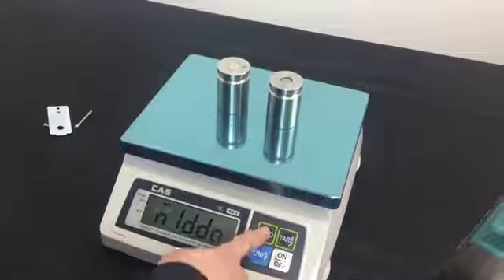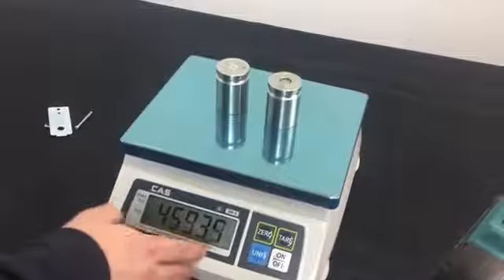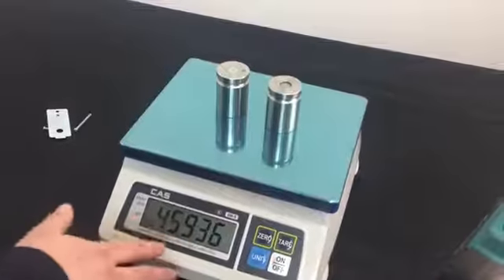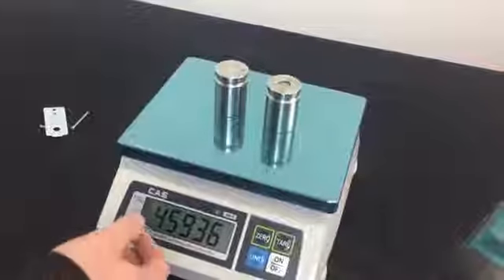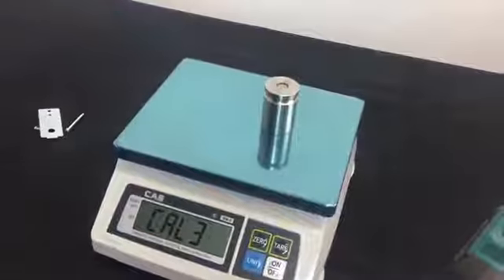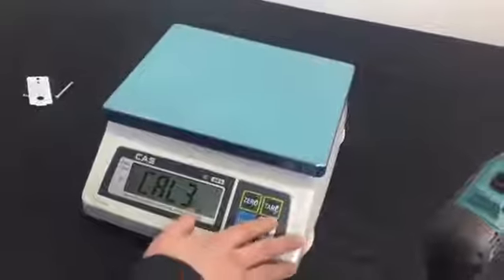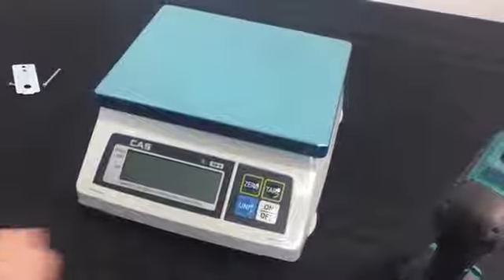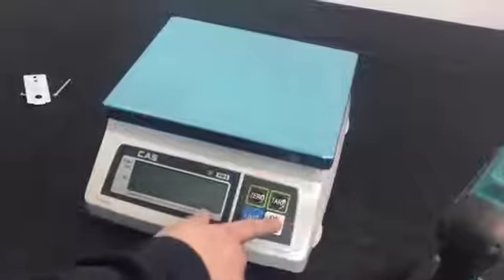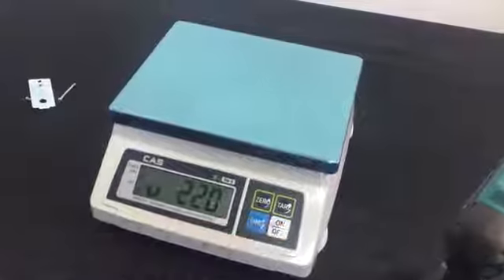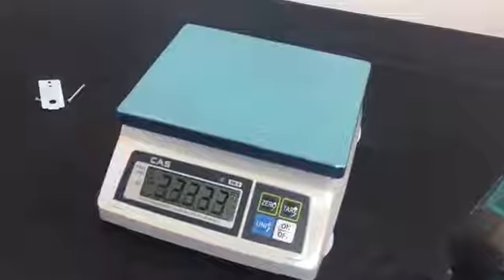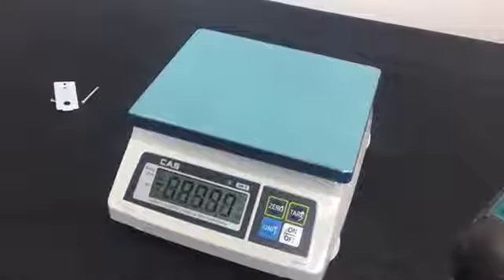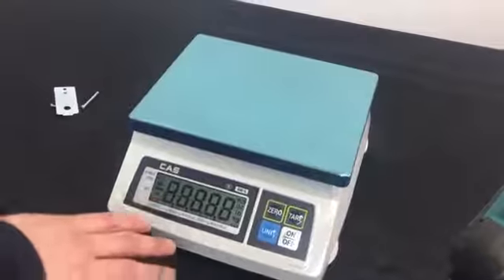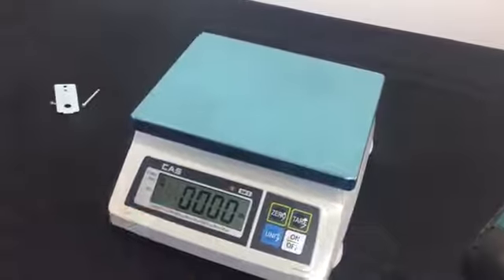Now we go back to the middle weight for our 3-point calibration. 2 pounds again. Press the 0 key. Now we see our weight. Now our raw counts are good. And done. Shows Cal 3 on the menu. Now all you want to do is push the power key off, turn the scale off. Now to test your weight, just turn the scale simply back on. Wait for it to count up. Once we get to stable at 0, test your weight.